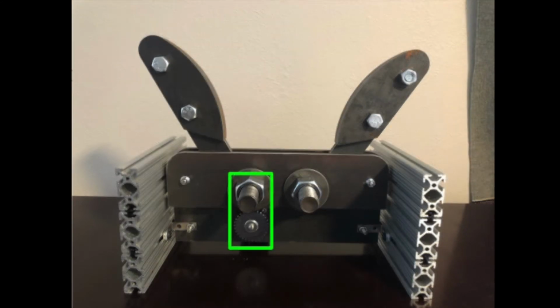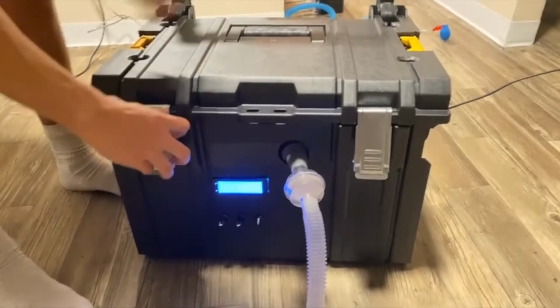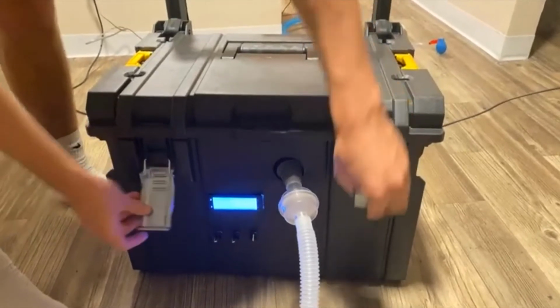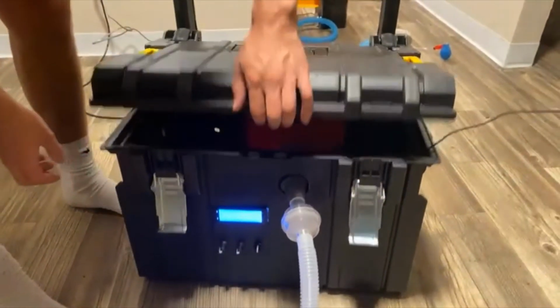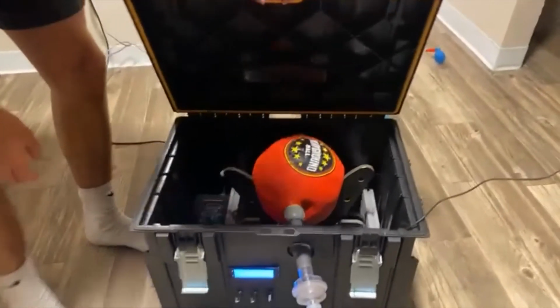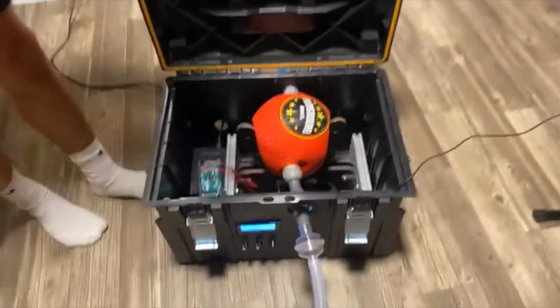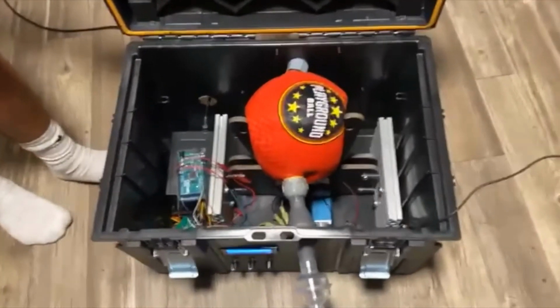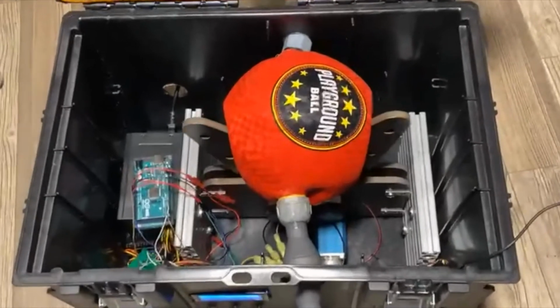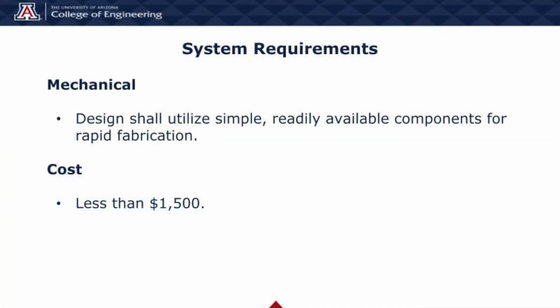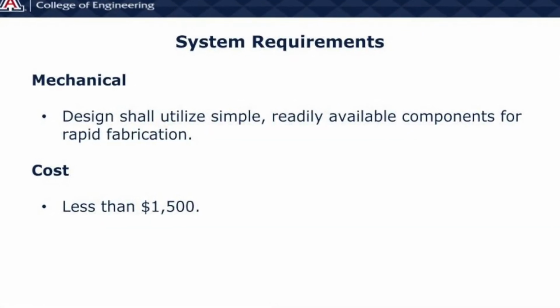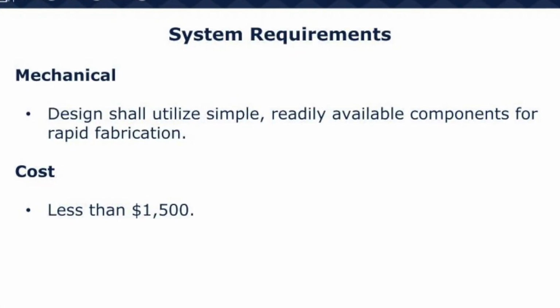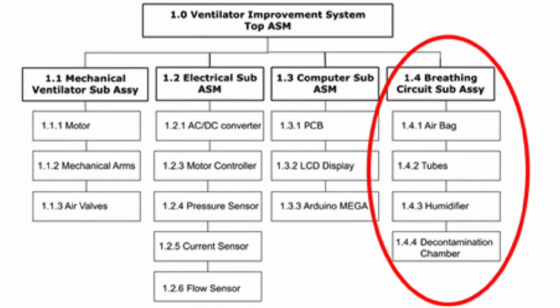When the ventilation program is turned on, the arms are in the outward or decompressed position. The motor pinion turns counterclockwise to simultaneously move both arms toward the center to compress the air reservoir and send it to the patient. The motor pinion then rotates clockwise to decompress the reservoir and move the arms outward for the next cycle. This process automates what is known as manual resuscitation, which satisfies the requirements of producing a low-cost and rapidly manufactured device. Next, we have the breathing circuit subassembly for our mechanical ventilator system.